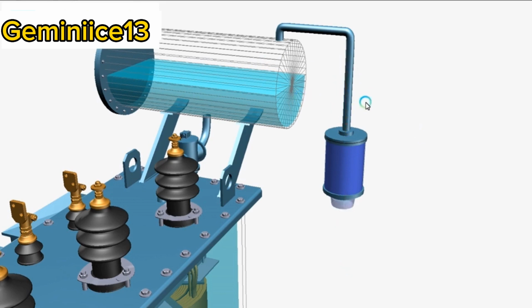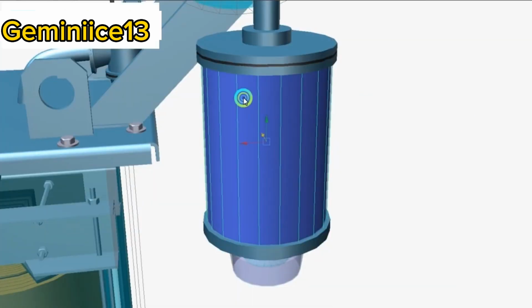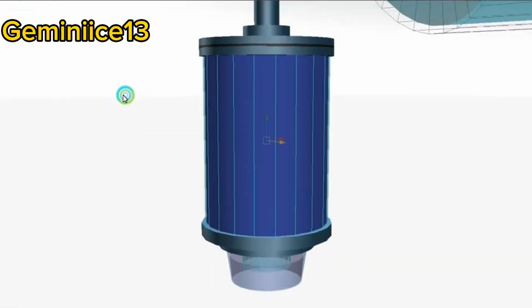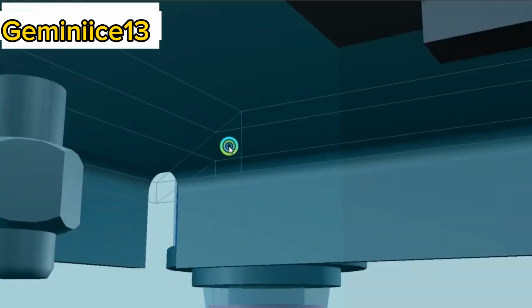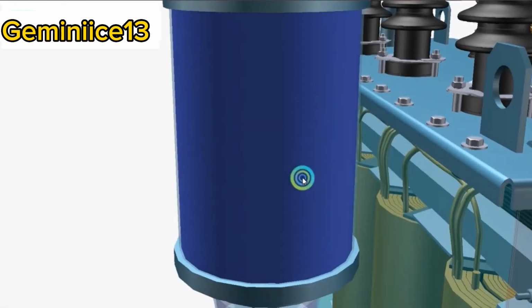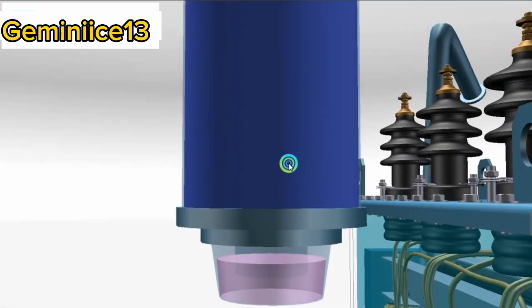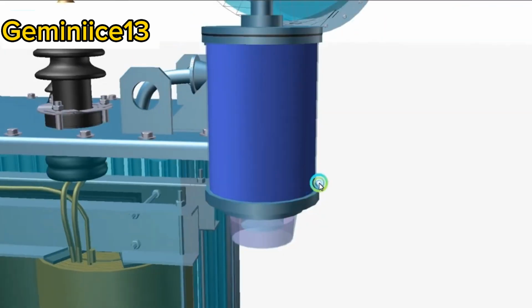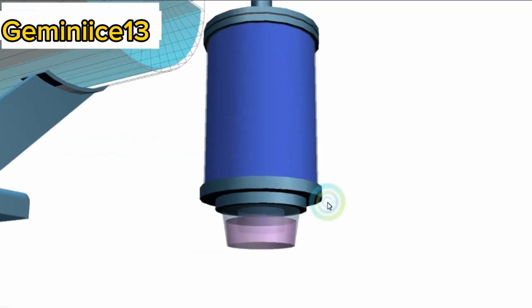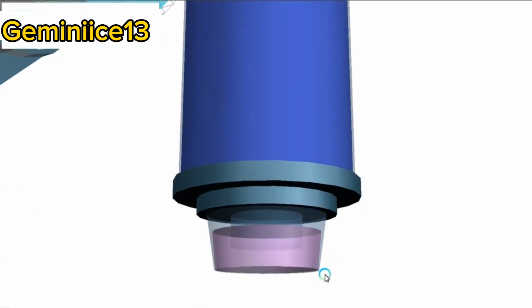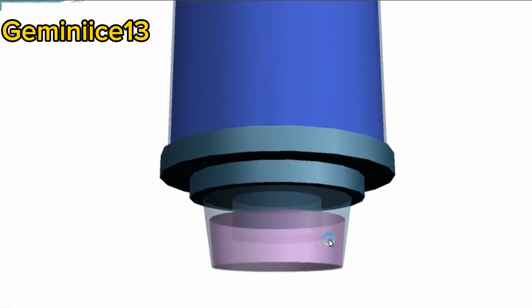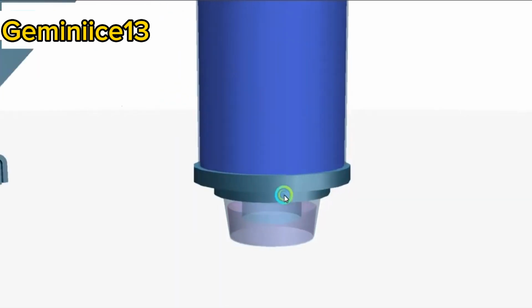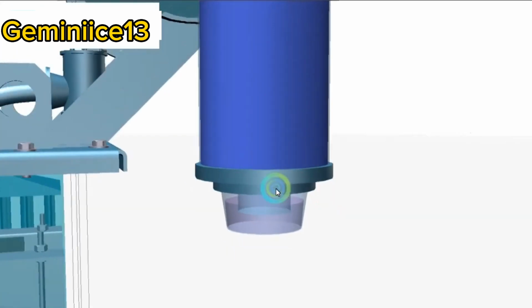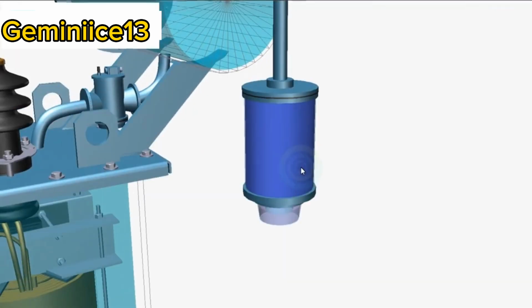Normally the incoming air may consist of moisture and dirt, and it may cause different types of damage inside the transformer. So that's why silica gel is used inside the breather. When the air enters the transformer through this breather, the silica gel absorbs the moisture. Only dry air enters into the transformer. So here you can see it. This breather also has an oil cup fitted, so that the dust particles get settled in the cup. Okay, so oil is used for dust. Silica gel is used for moisture and oil is used for dust. Both are cleaned by this process, and only dry air can enter the transformer.